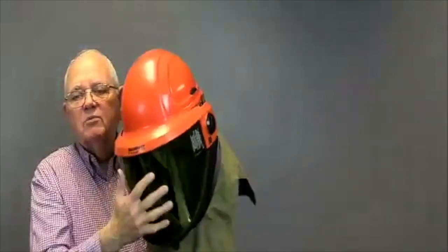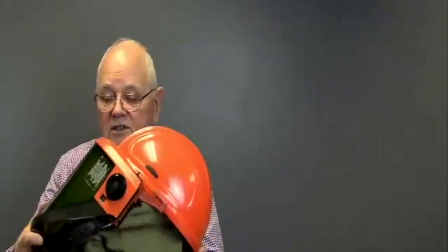Now, of course, you're going to do your regular inspection and so forth, make sure everything works properly and is not damaged. You do want to look at the specific label. Don't go by what's just on the outside of the garment. When you look at the label, you're looking for one of two items: either the arc thermal performance value, the ATPV, or the energy break open threshold, the EBT. You're going to use the lower of those two numbers to determine the arc rating of your garment. But I can tell you from the real world, probably 90% of the time or better, when I've looked in garments, I find just the ATPV rating. So you'll want to use that and do a visual inspection.